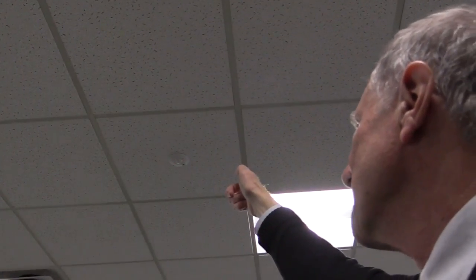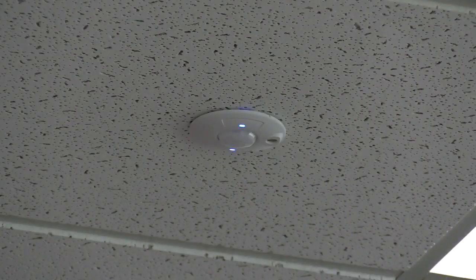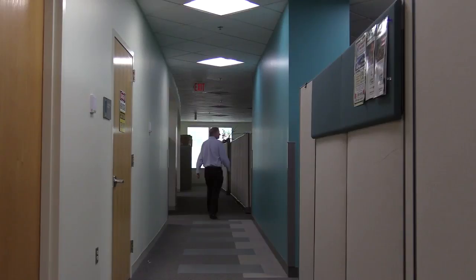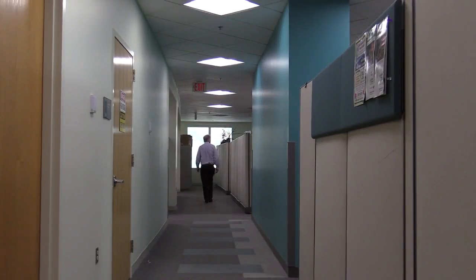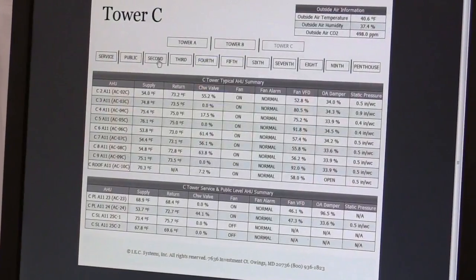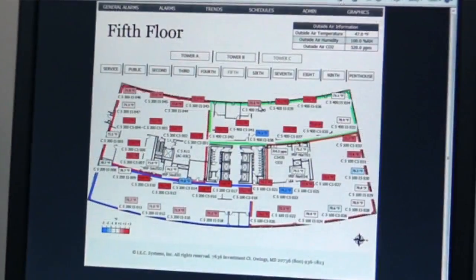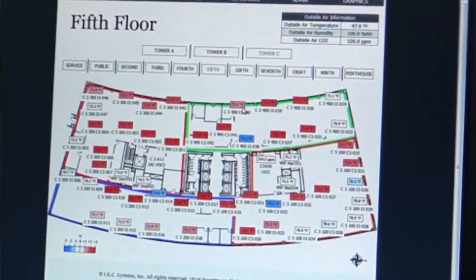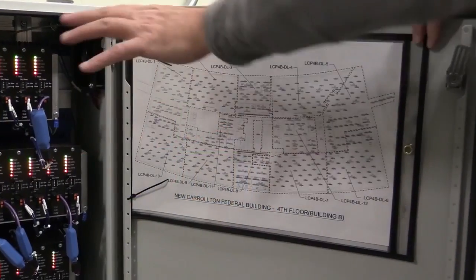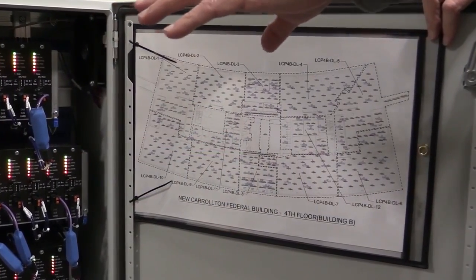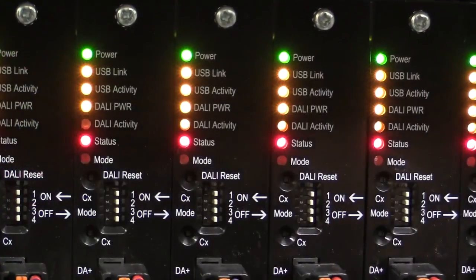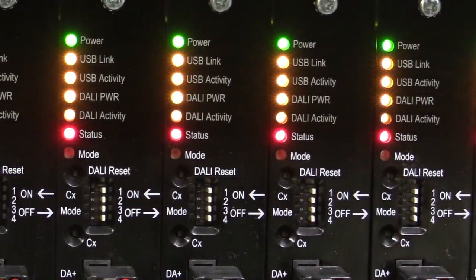motion and ambient light. This is an occupancy sensor in the ceiling. It senses whether anybody is present in the space, which will turn the lights on and off, and it will also communicate with the building automation system, and the temperatures will vary according to occupancy. The old lighting system was replaced with an open protocol, digitally addressable lighting system, or DALI system.